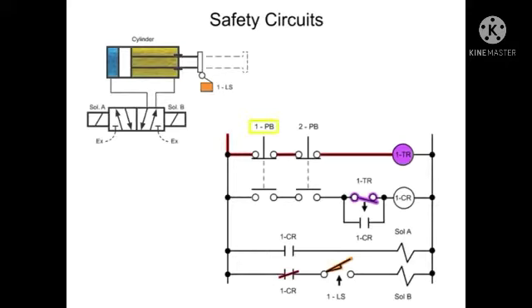If an operator depresses a single push button, power to the timing relay is removed, and the off-delay timer starts to time. Only when an operator depresses both buttons within the off-delay timer countdown period can power flow to the 1CR contact relay and energize the bypass circuit.